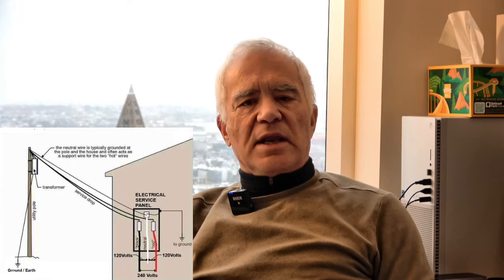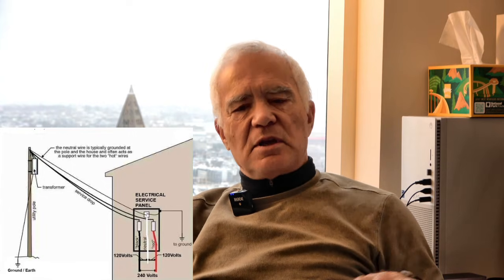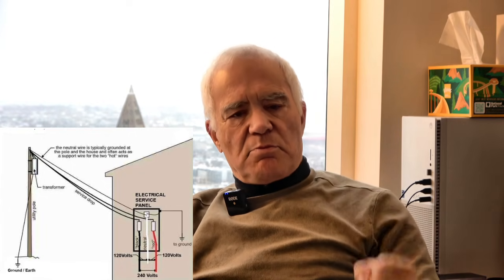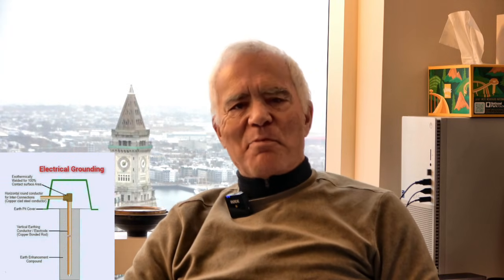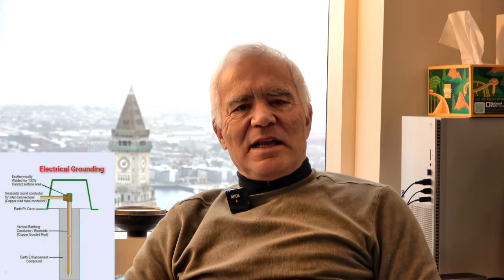What is more of an issue is in the US, they still think in terms of 120 volts, I think because that's what people have in their houses. But the problem is all the houses are actually fed 240 at the outset. Once they feed the power into a house, they put a copper pipe ground in the ground and create their own neutral. They bind the neutral and the ground at the start of the house, and then feed the whole house with what we think is 120, but in fact it's 240 everywhere with a split in the middle.